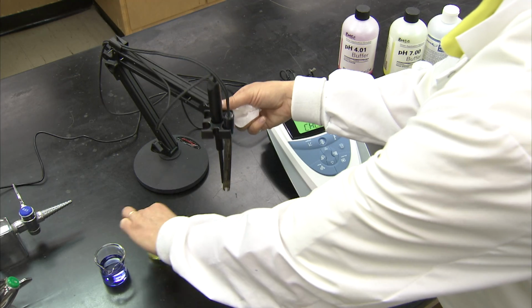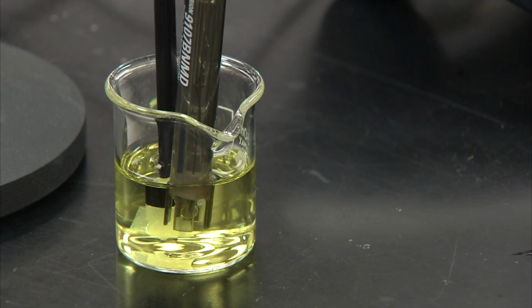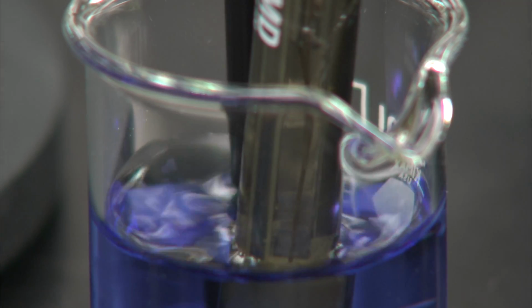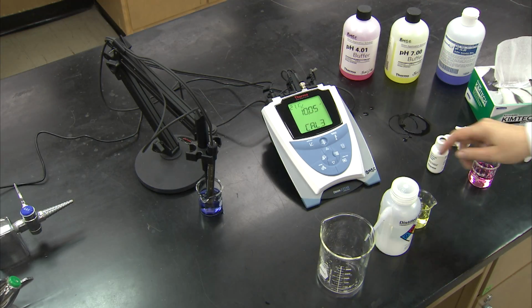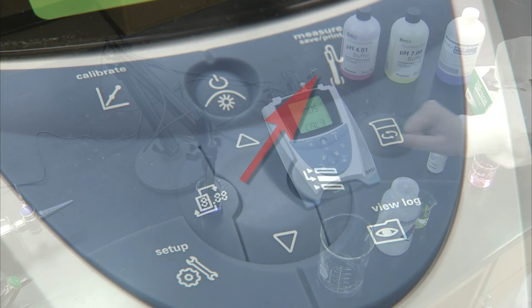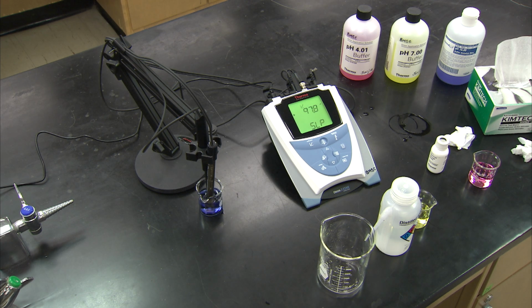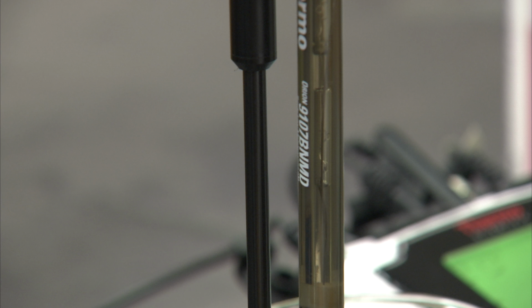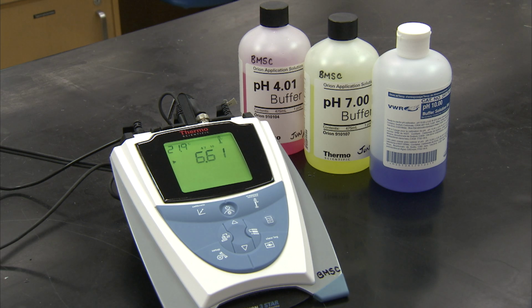These steps will be repeated for the pH 7 and pH 10 standards, except at the end of the pH 10 calibration, the Measure Save button will be pressed instead of the Calibrate button. Once the calibration is done, the slope of the standard curve is calculated and given as a percentage of the theoretical optimum for that probe. As a probe ages, it will usually become less accurate and responsive, and the percentage will drop. A guideline is that a probe with a slope below 90% should not be used.